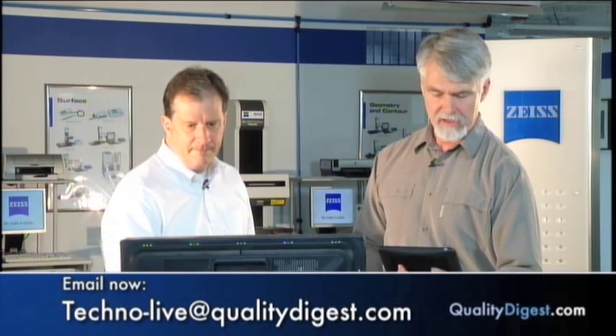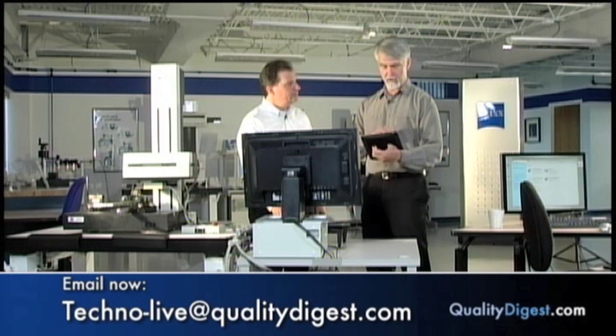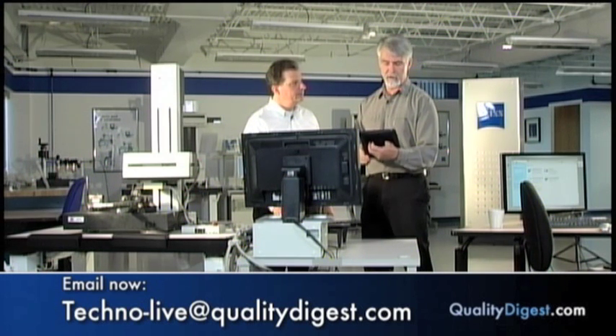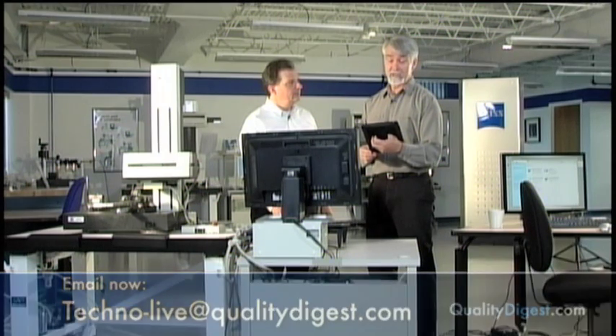Okay. Another question, this one's from Daniel. It's another TIMS related question, but from the hardware end. We are using TIMS software and would like to upgrade, but would like to know if we would need new computers and or controllers. It all depends on the age of the instrument that you have. Many times, if it's relatively recent, say in the last 5 years maybe, it might just be a PC upgrade and not a hardware upgrade. If it's older than that, we're probably looking at also some hardware that we have to replace for the communication between the computer and the instrument.